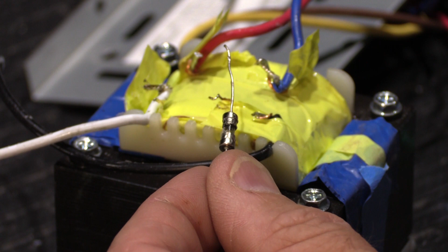So I cleaned it off without scratching it up too much and looked at it under the microscope - it read 1.5 amps. I did a quick calculation for the input fuse rating for a transformer of this size, and 1.5 amps seems about right. It could have been 2 amps and still been okay, but we're not going to modify it because this is what it was UL rated for - or in this case ETL rated, which is really the same thing. It's not proper for us to change from what they specified.